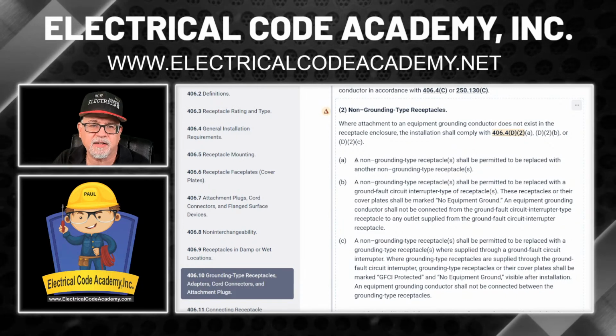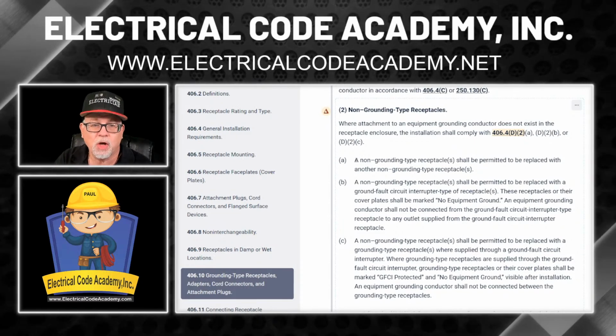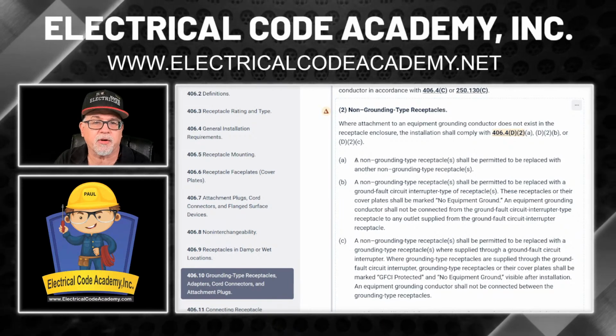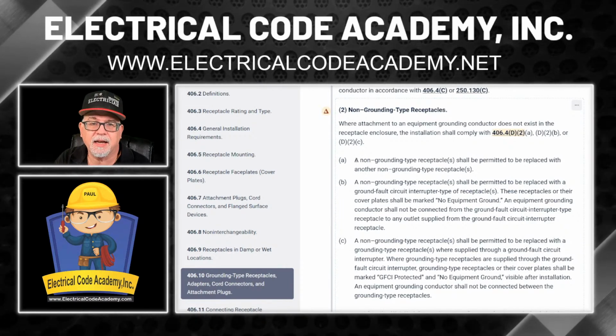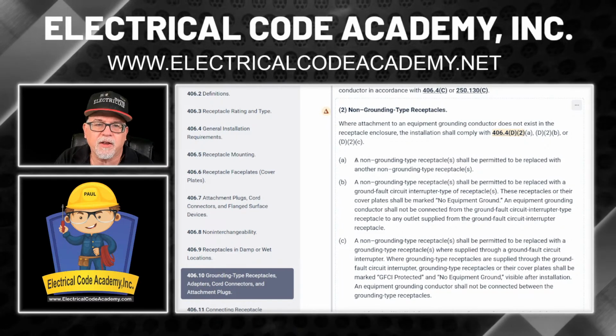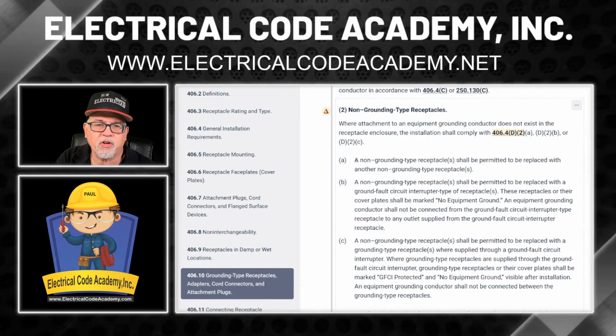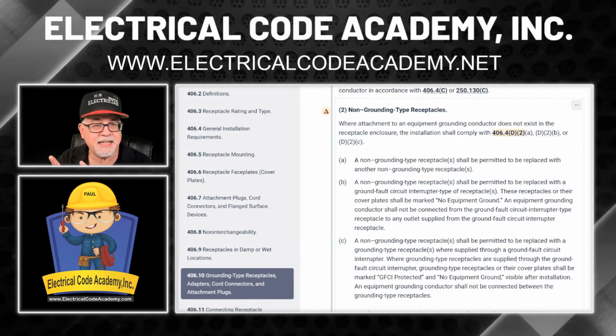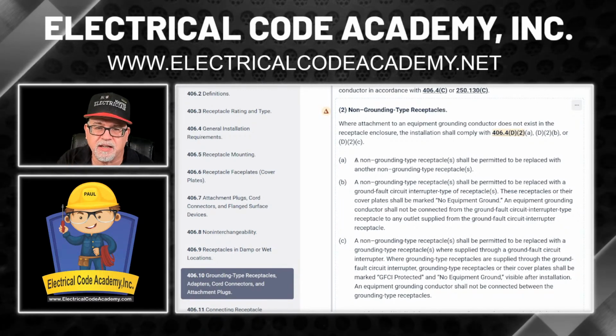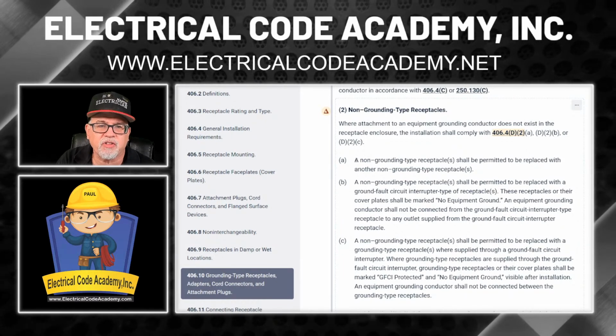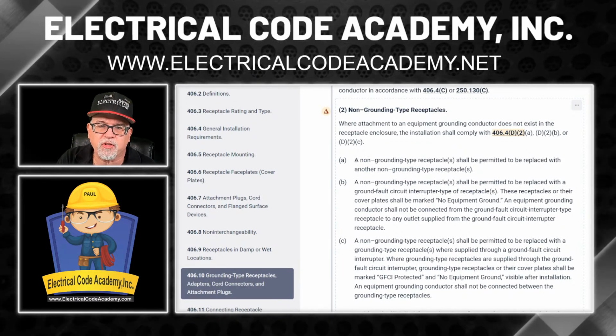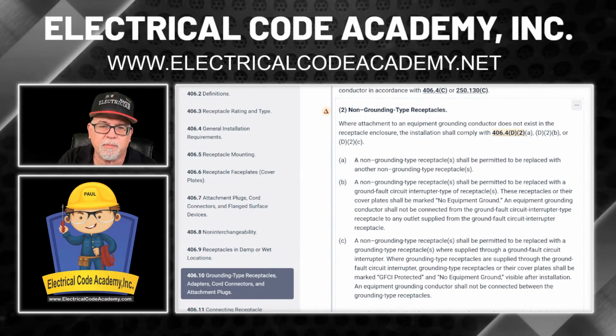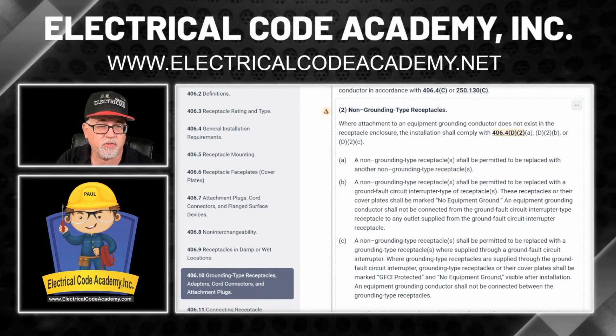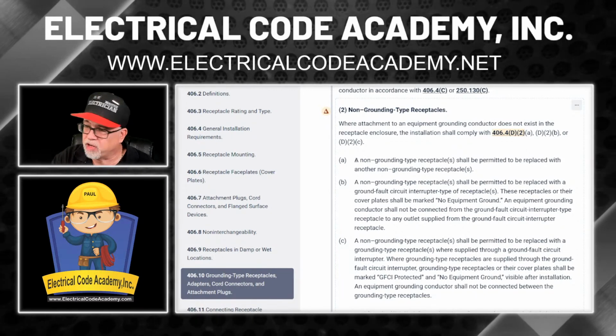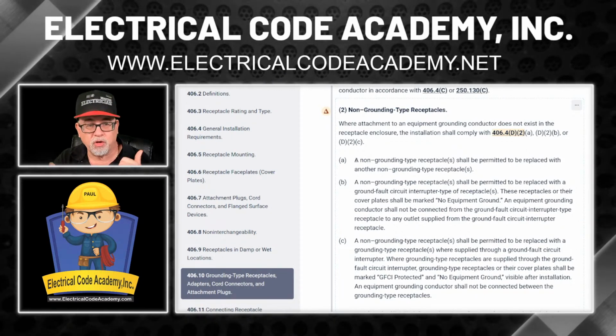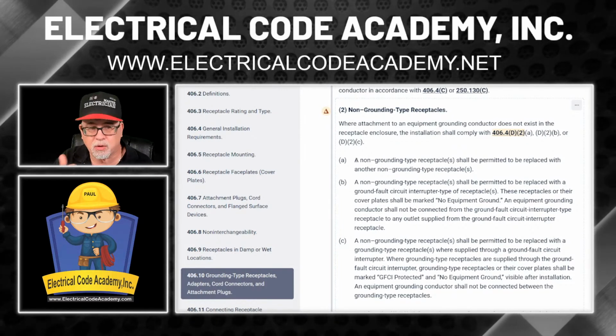It says, non-grounded type receptacles shall be permitted to be replaced with a ground fault circuit interrupter type of receptacle. That's what he did. Okay? It says these receptacles or their cover plates shall be marked no equipment ground. And that's what he did. He put the little label that comes with the GFCI. He's good. Then it goes on to say, an equipment grounding conductor shall not be connected from the ground fault circuit interrupter type receptacle to any outlet supplied from the ground fault circuit interrupter. So if you're extending from that one onto another one and you're thinking, oh, well, now I'm going to use the right type of wire and cable that does have an equipment ground.